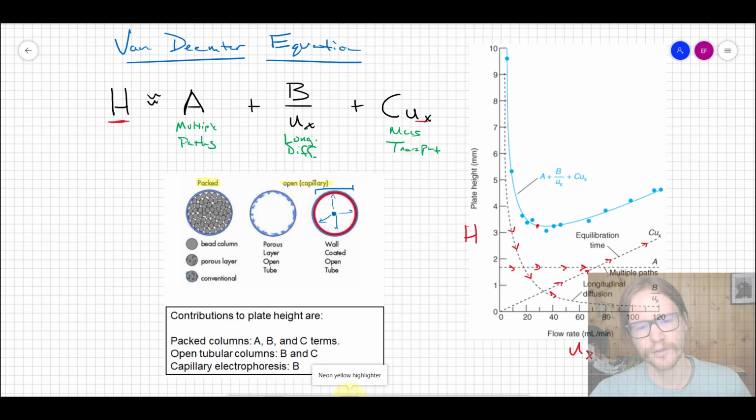The good part about capillary tubes is they can be super long. As we talk about gas chromatography, I'll show you a capillary column that's 30 to 50 meters, so we're talking about 150-ish feet long that we're separating gases over in this open tube capillary, whereas a UPLC column that we use on the ultra high pressure liquid chromatography system may be on the order of less than 10 centimeters long, but its diameter is on the order of 1 centimeter as opposed to tens or hundreds of microns.